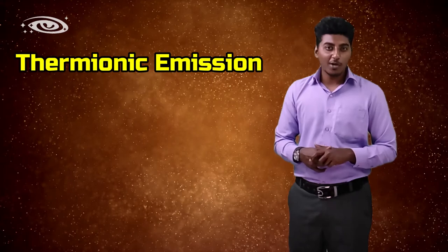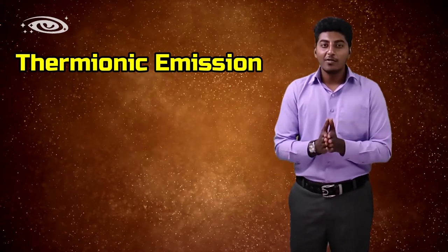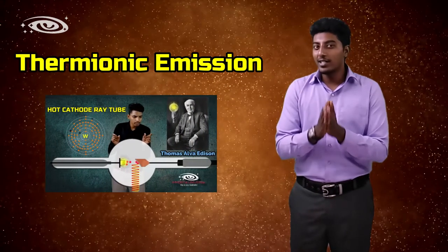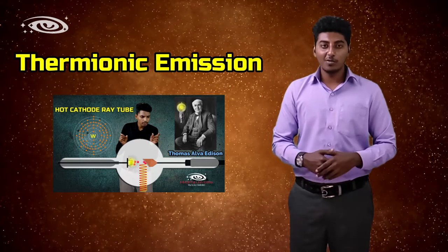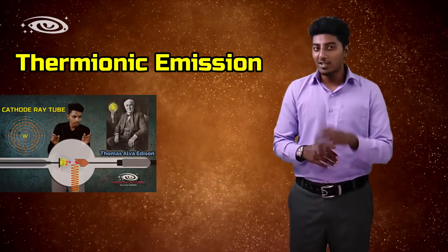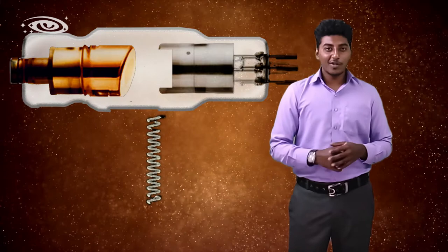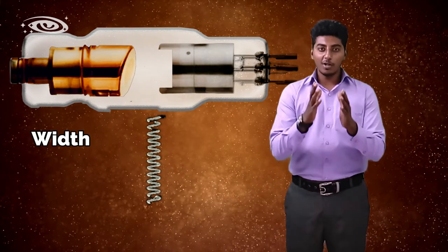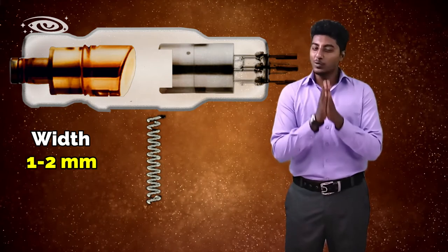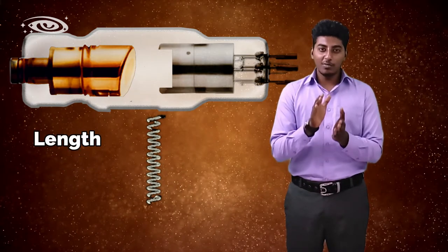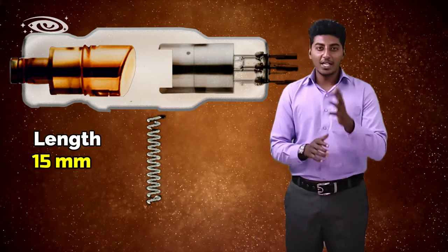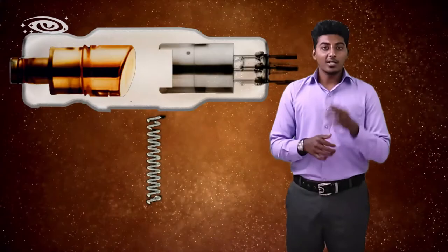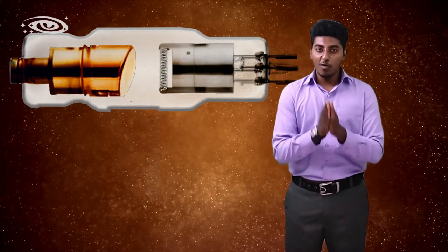If you want to know the thermionic emission principle in detail, we have done a video for that with a link in the description box. You can check it out after this video. The thickness of the filament wire is 0.1 to 0.2 millimeter, the width of the coil is 1 to 2 millimeter, and the length is 15 millimeter. This filament is fixed inside the focusing cup.